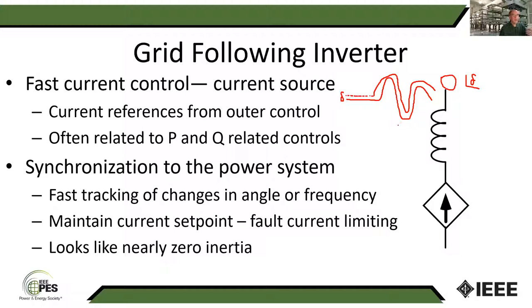And so if you're connected to a microgrid, most of the time any power converters that you have for generation sources on a microgrid would be running in this grid following mode. But if we get into a situation where the microgrid has become isolated from the power system, you can't do this, because you've got to have somebody who's a master for setting the frequency.